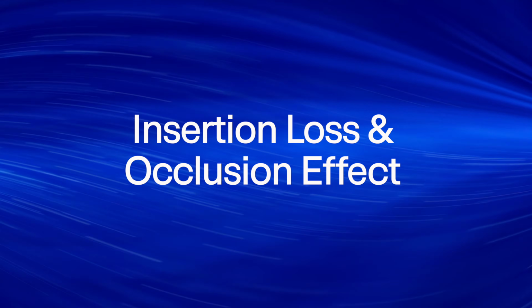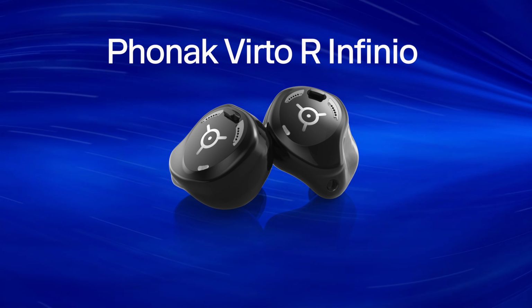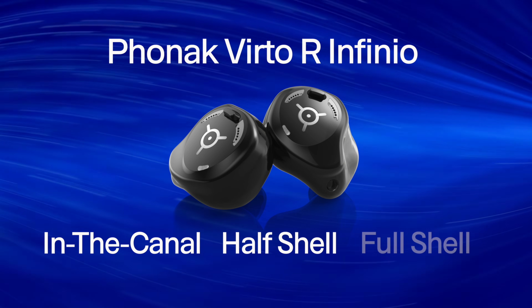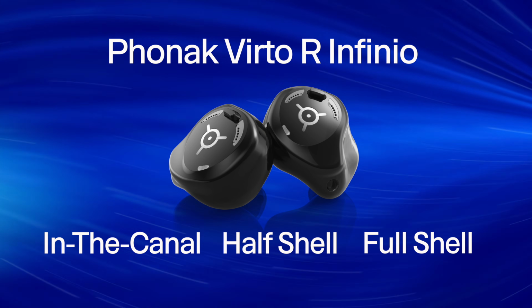Phonak also still uses acoustically optimized venting for the vents inside of your custom hearing aids to make sure that they minimize insertion loss as well as the occlusion effect. I've been a huge fan of acoustically optimized venting for years at this point, and when you combine acoustically optimized venting with acoustically optimized receiver selection as well as biometric calibration of these hearing aids, you have an excellent hearing aid to work with. This also means that the Virto R Infinio hearing aid will come in either an in the canal, half shell, or full shell hearing aid based on these different variables, with the goal of making these hearing aids as small as humanly possible without sacrificing performance.